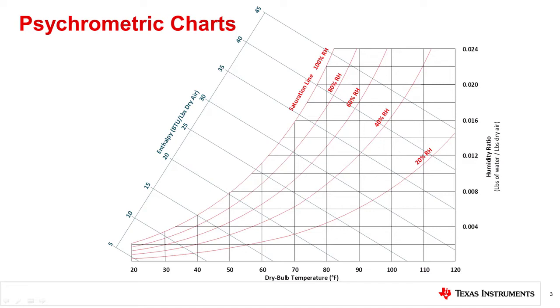A psychrometric chart shows the relationship between the parameters we just defined. The x-axis typically displays the dry bulb temperature and the y-axis displays humidity mixing ratio. Additional values such as dew point, vapor pressure, enthalpy, absolute humidity, and relative humidity may or may not be displayed depending on the specific chart. For any psychrometric chart, knowing any two parameters will allow you to locate a position on the curve that corresponds with all other labeled values.